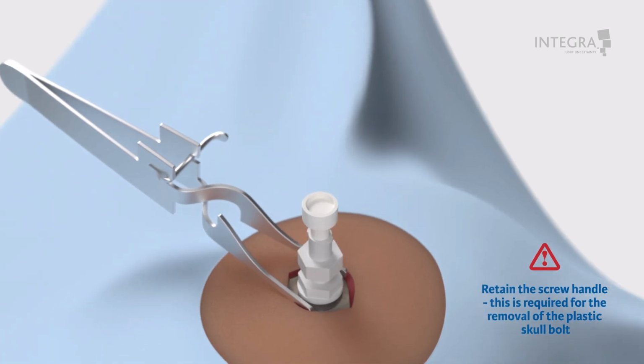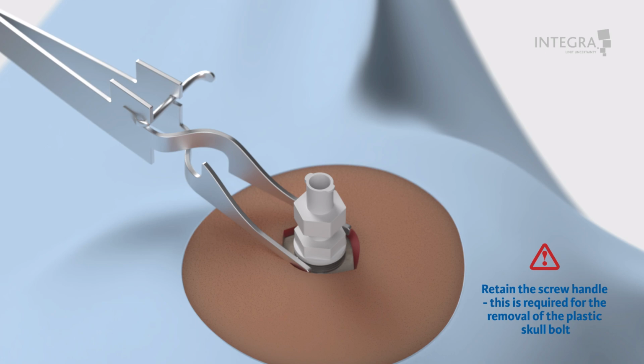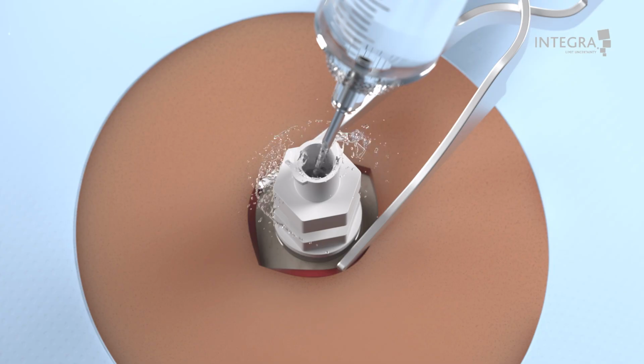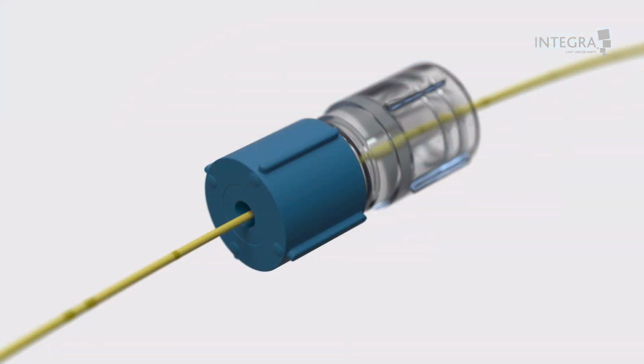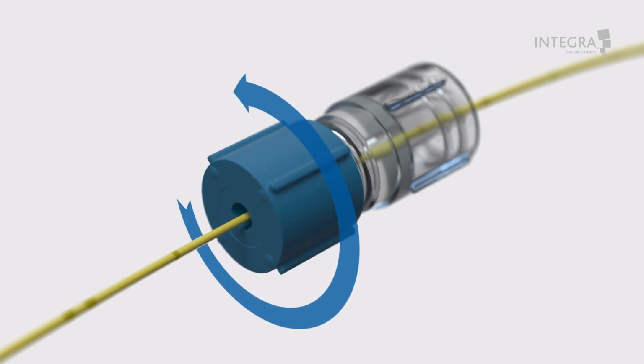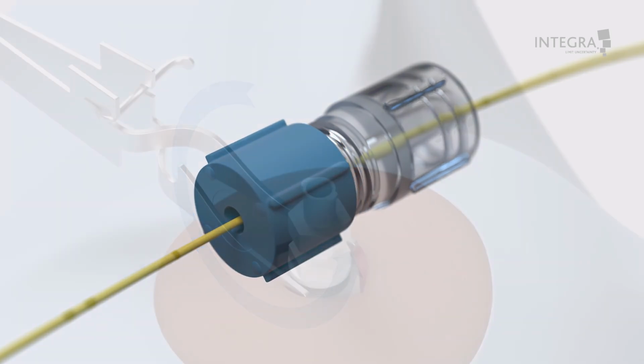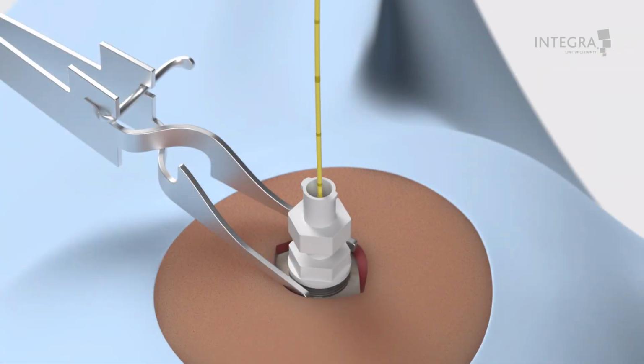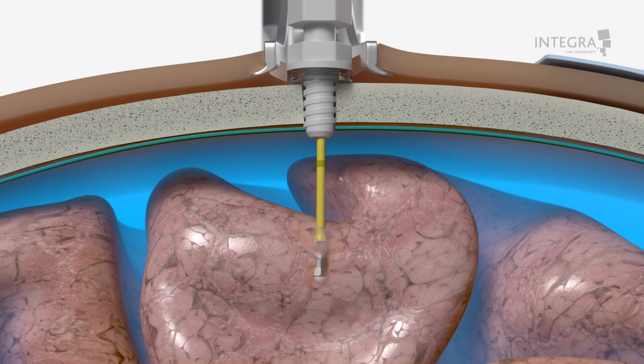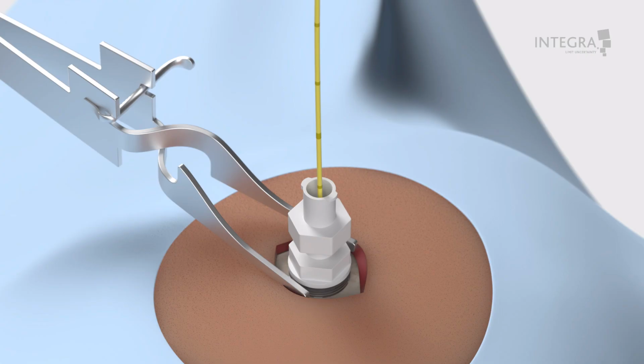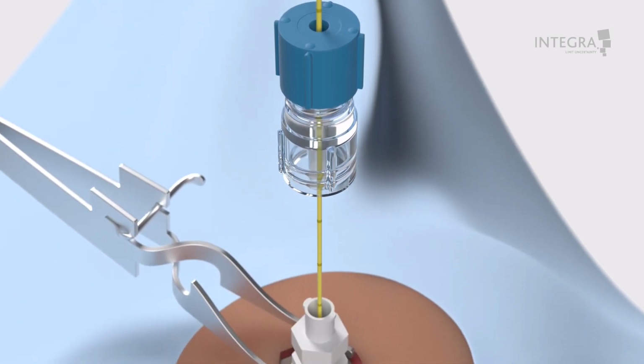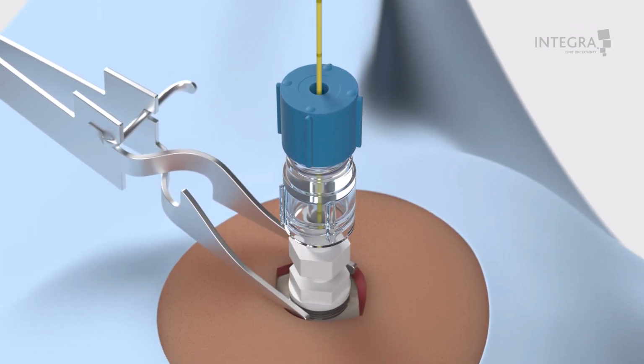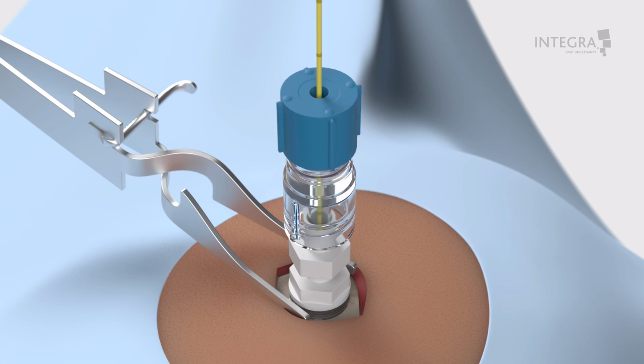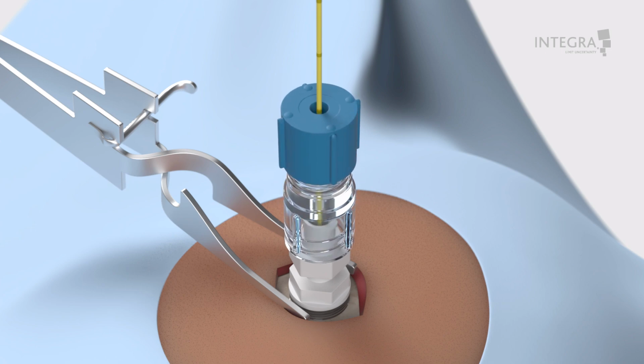Remove the screw handle. Remove the obturator from the positioned plastic skull bolt. Irrigate the channel with non-bacteriostatic, preservative-free sterile saline. Loosen the Tuohy-Borst adapter from the ICP sensor by twisting the blue adapter counterclockwise. Guide the ICP sensor through the bolt until the tip is in the subdural or parenchymal space, using the depth markers on the sensor as guidance. Slide the Tuohy-Borst adapter down the ICP sensor until you reach the implanted plastic bolt. Screw the Tuohy-Borst adapter onto the plastic bolt. Turn the blue adapter clockwise to secure.